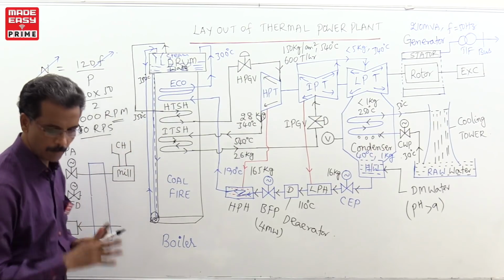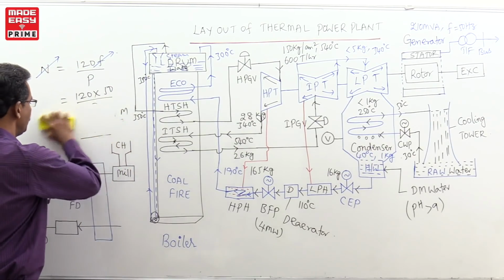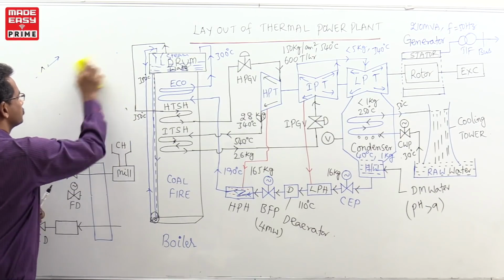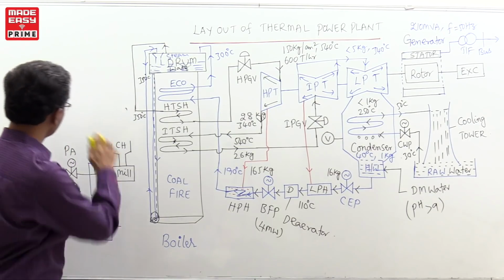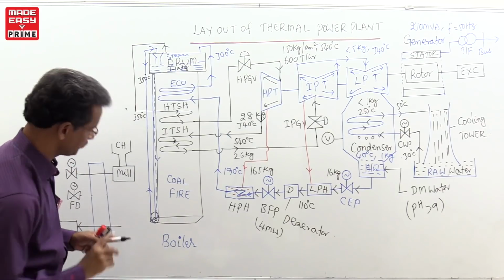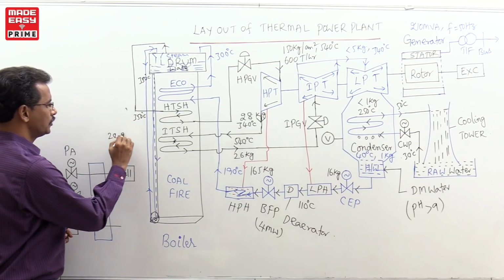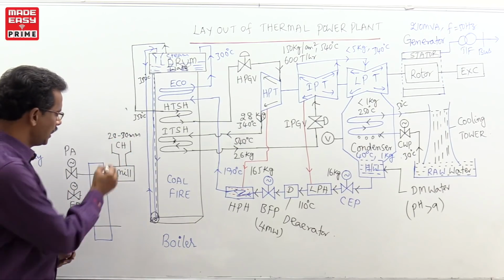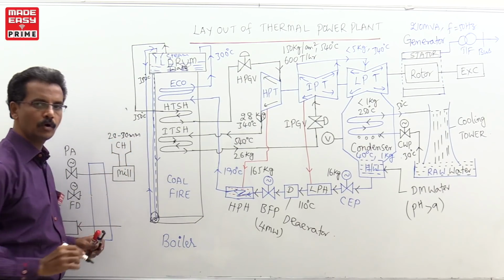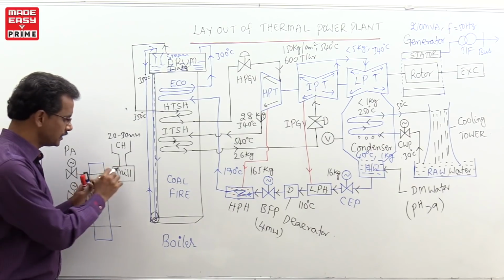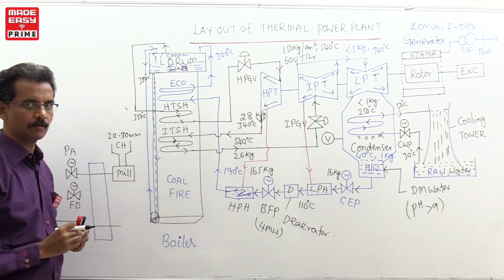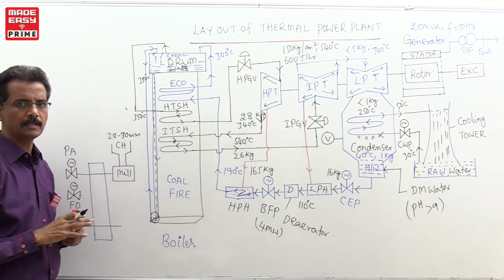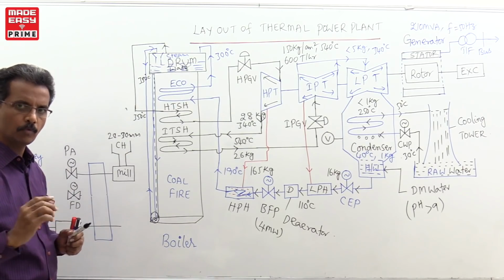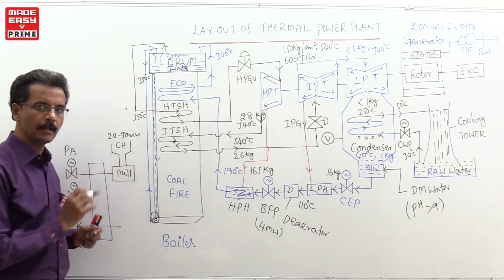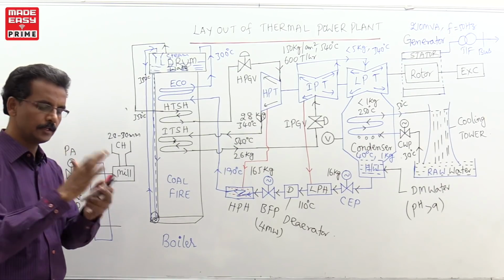Inside this coal hopper, normally we maintain coal of around 20 to 30 mm size. From the coal hopper, we are sending the coal into the mill. Normally ball mills are now used. Two types of mills are there, one is the bowl mill, another is the ball mill. In most generating stations, we are using ball mills.